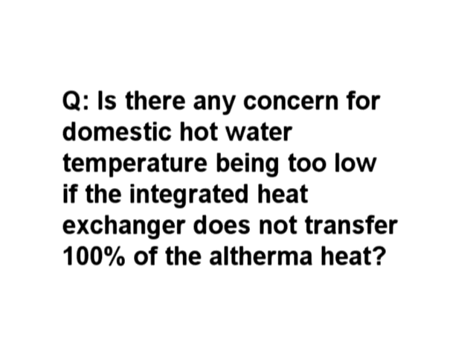Yes, I have a question about domestic hot water temperature being too low if integrated with a heat exchanger. That is a low temperature going into that heat exchanger in the indirect water heater. That's why the recovery rates are slow, and that you will have times where, if you want to go above 120 degrees, you'll have to use the booster for a very short period of time. But keep in mind, that's a very small amount of energy, actually, to boost it from 120 to, let's say, 125 or 130, in terms of the capacity of the tank. So that's why I do point out that storage is the best way to manage load profiles when you're dealing with these kinds of units.